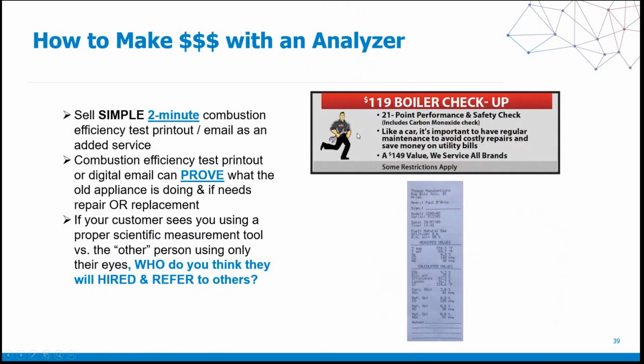How to make money with an analyzer. One of the things that a technician can do is to basically sell a simple 2-minute combustion test as a level of service, because chances are your competition is not doing it. You're going to alert a homeowner or business owner to potential problems with their system, but you're also going to justify if the piece of equipment is working at the efficiency level that they thought that they were paying for. And then you could possibly make adjustments to that system to bring them to within that efficiency level, whether it's different adjustments to the system, gas pressure, and the like.